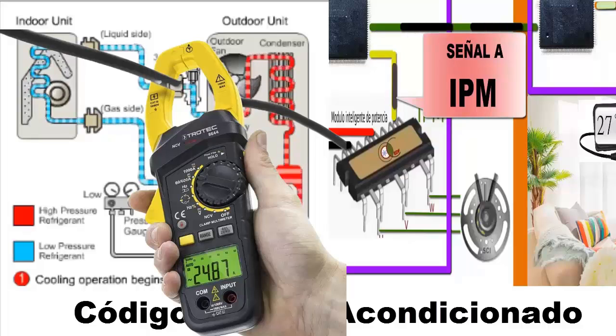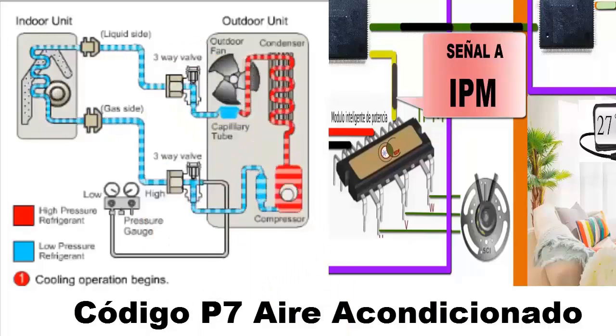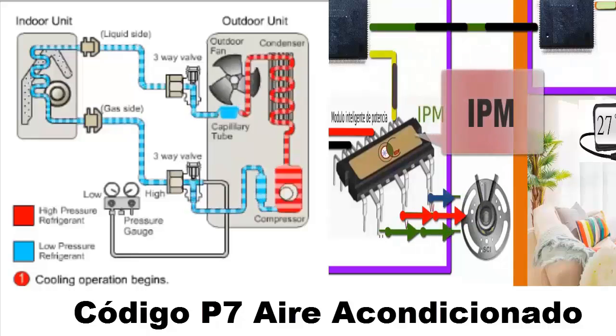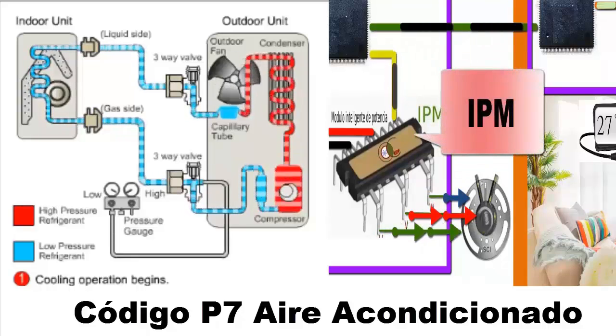Excess current consumed by the compressor is often related to refrigerant pressures out of range, a blocked capillary tube, or a dirty or poorly positioned condenser.